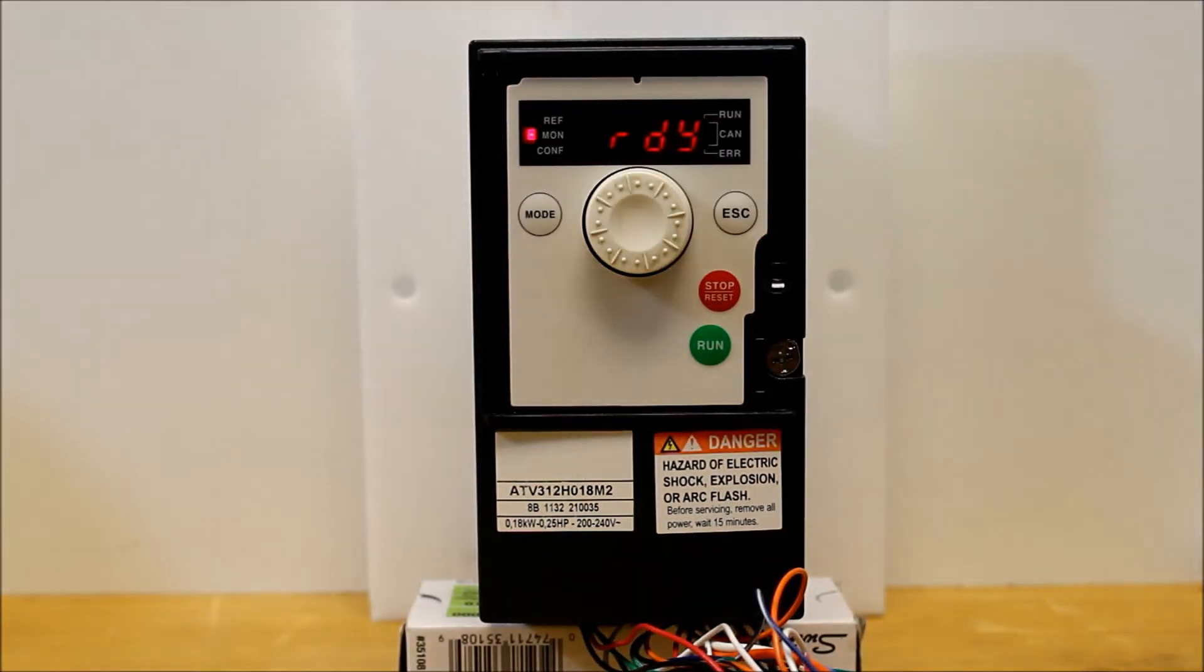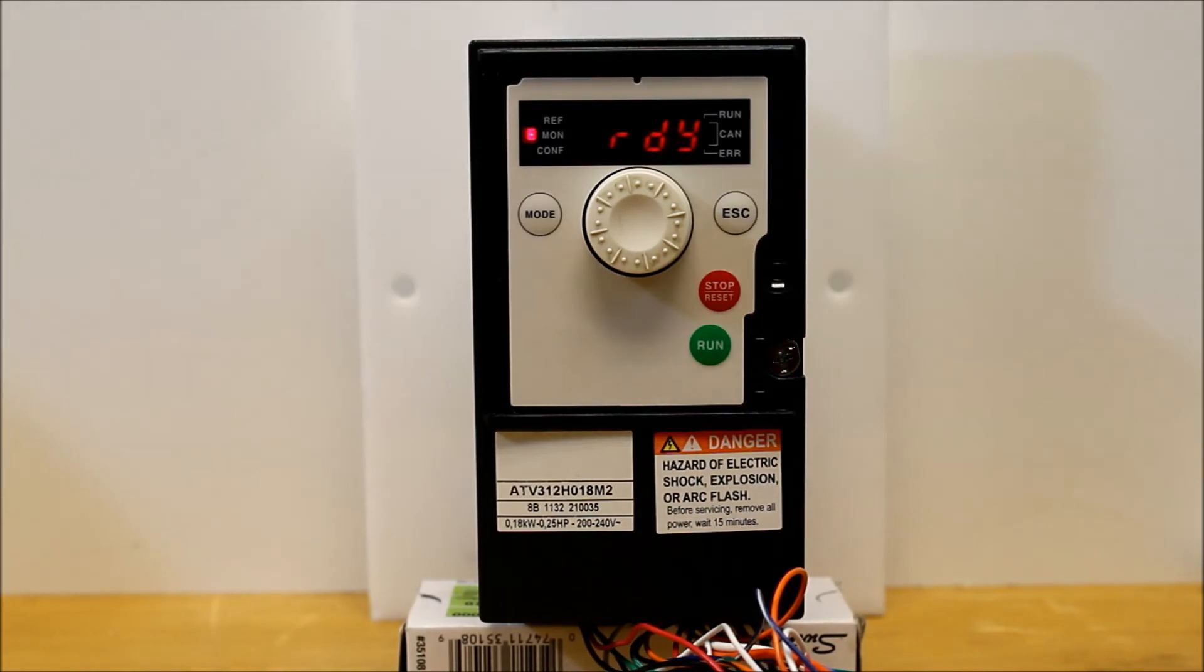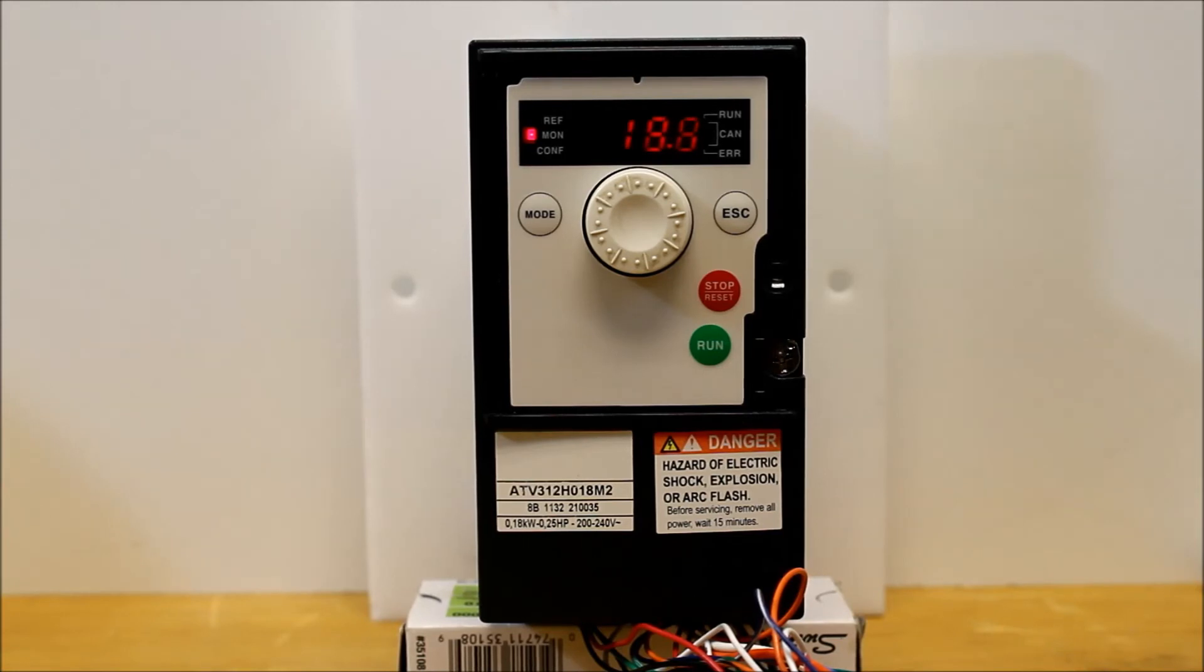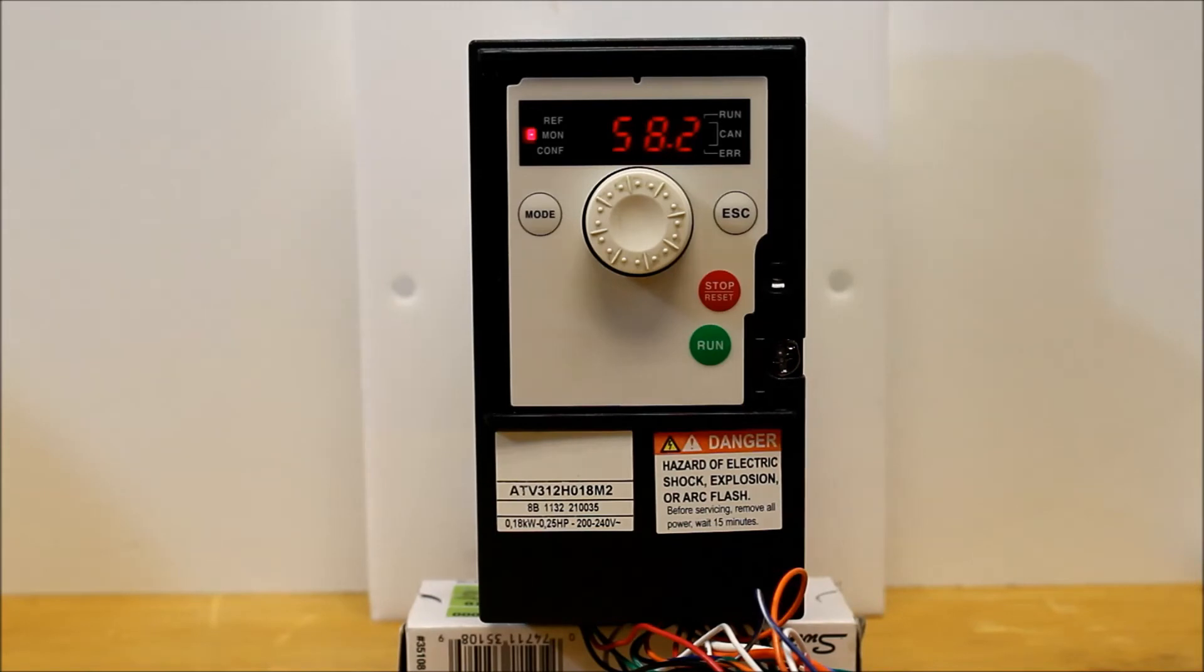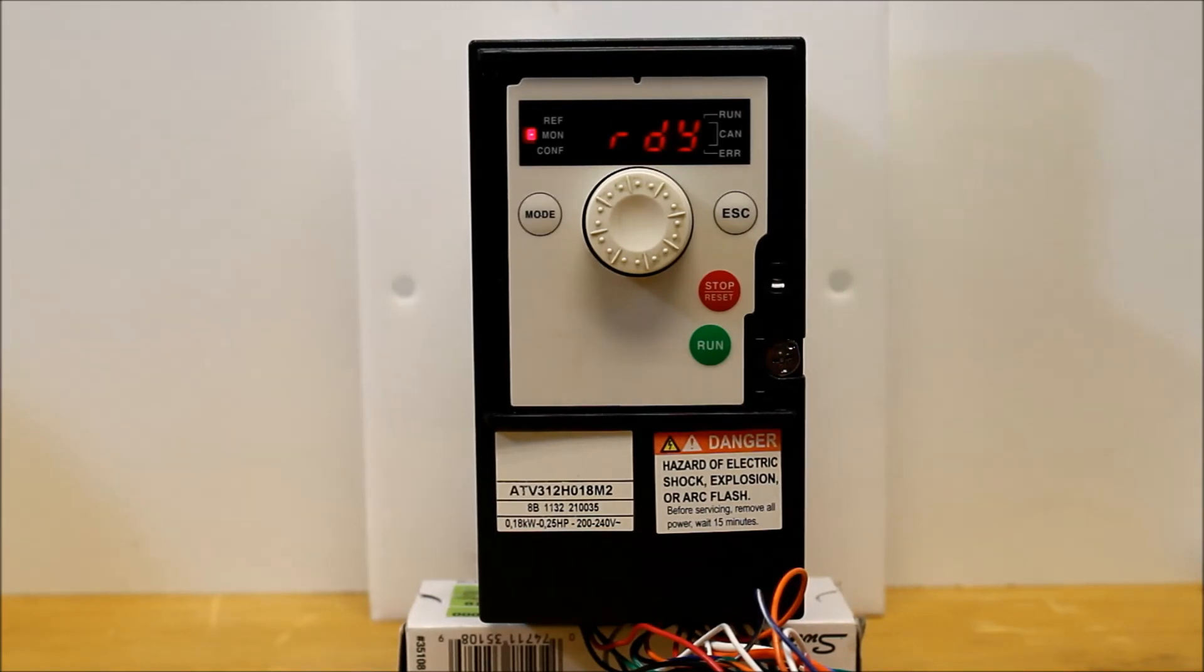And like I said, LI1 is your run forward command on this drive for two-wire control. So we can toggle it. And as you can tell, it starts ramping up your drive. And now we can remove the 24 DC off of LI1, and it will go back to ready.